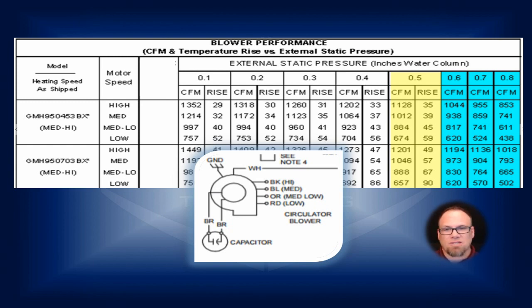Okay, now the manufacturer has on their tag 35 to 65 or 30 to 60. Okay, but that's an operating range that's safe to operate that piece of equipment. That doesn't tell you anything about efficiency or anything like that. You still got to set it up. Okay, so older furnaces had a temperature rise of around 100 degrees. Newer furnaces of the same BTU value are supposed to be set up around 50 degrees. So what changed? We went from 100 degrees temp rise on the old one to 50 degree temp rise on the new ones, a ton more airflow. That's what we've got to move, is a ton more airflow.